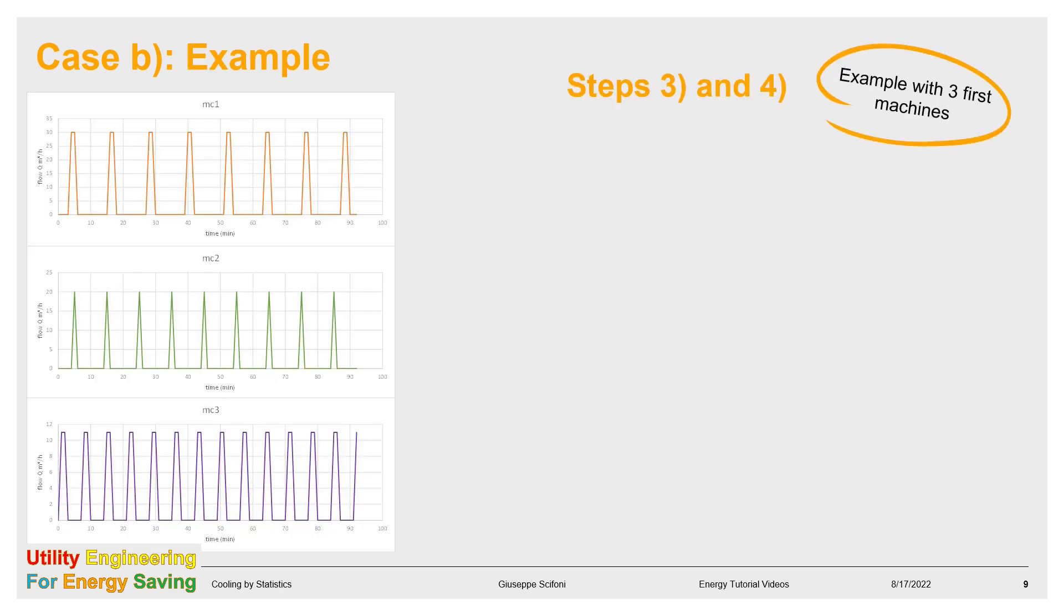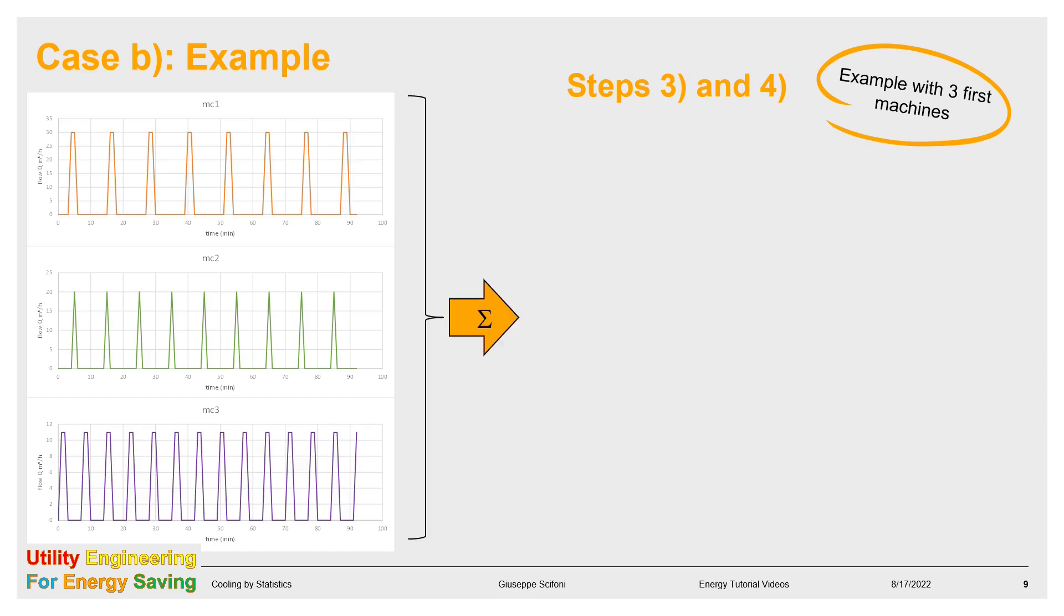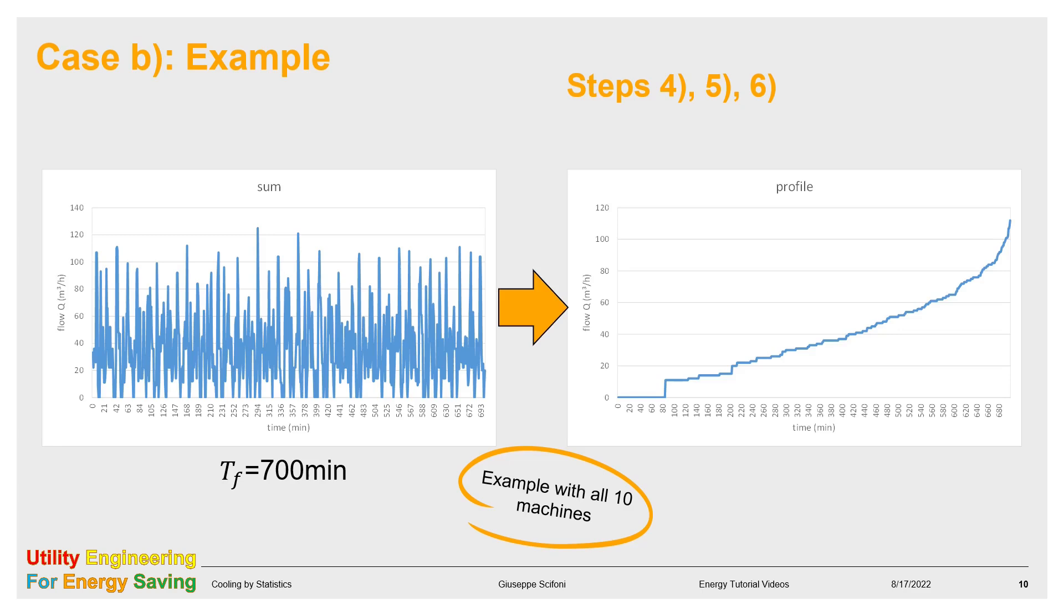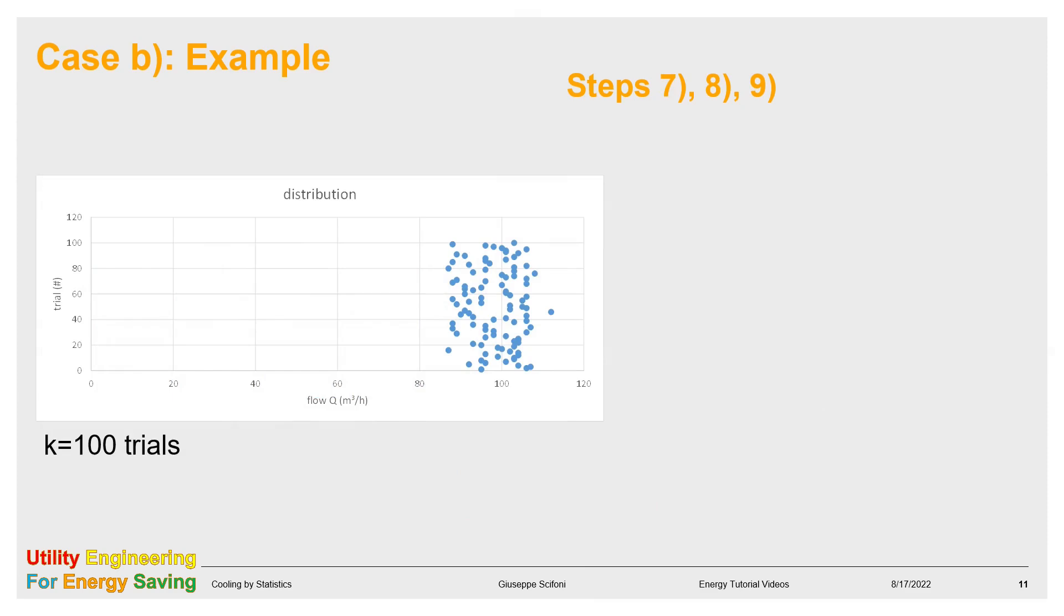Hereby the steps 3 and 4 from the above example, limited to the first 3 machines, to make the charts visible. Here the steps 4, 5, 6 with all 10 machines. From the sum, we generate the demand profile by sorting the value in ascent order. Then in the profile chart, we identify the 98% of the running time, and we find the corresponding flow, that is capital Q star. This procedure we have to repeat many times.